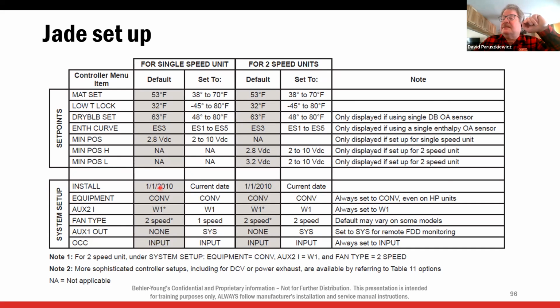You have to do the system install. That's just a date, which you can look back on to see when you put it in. Equipment type, conventional. Even on a heat pump, it's going to be conventional on equipment type. Aux2 in, W1. Why on earth is the W1 going to go to the economizer control? Because W1 is high speed blower, right? And if we've got G energized for circulation, we're on low speed blower. So when we flip to high speed for the heat, I need to make sure my damper adjusts to the high speed damper position because it's not as far open. So that's why W1 is actually going to send a signal to the economizer control.